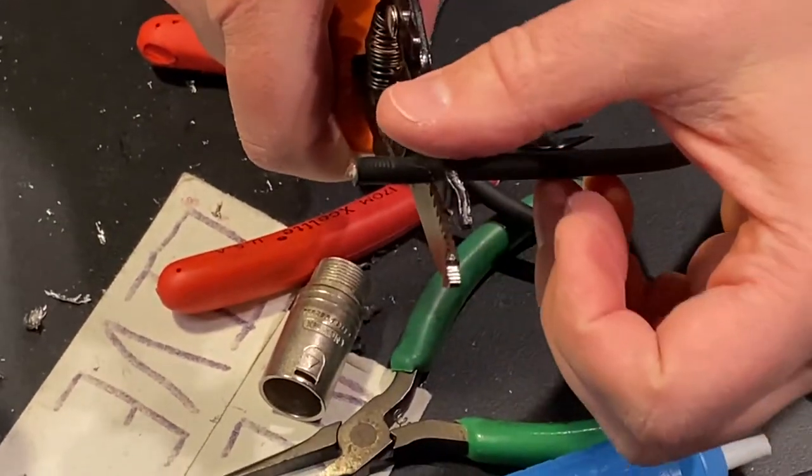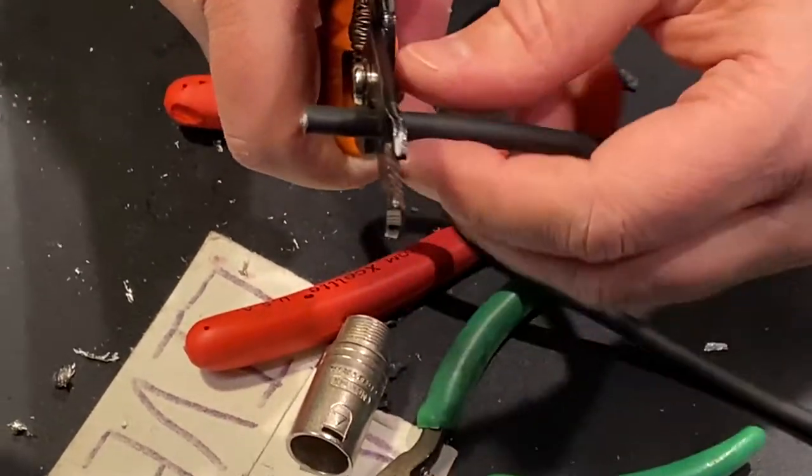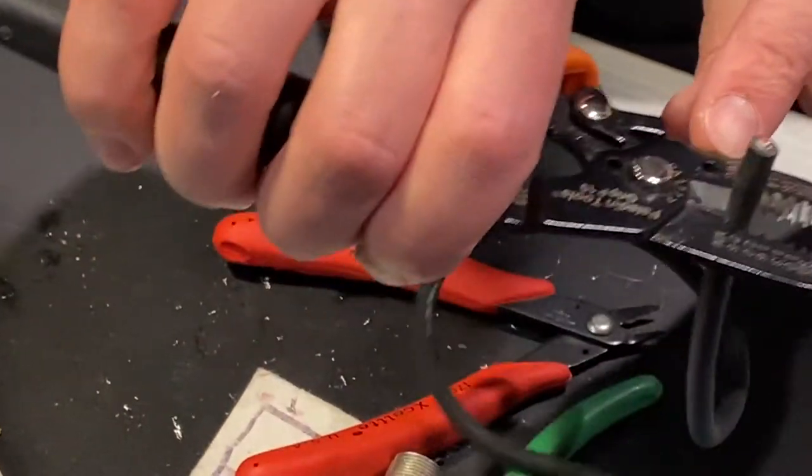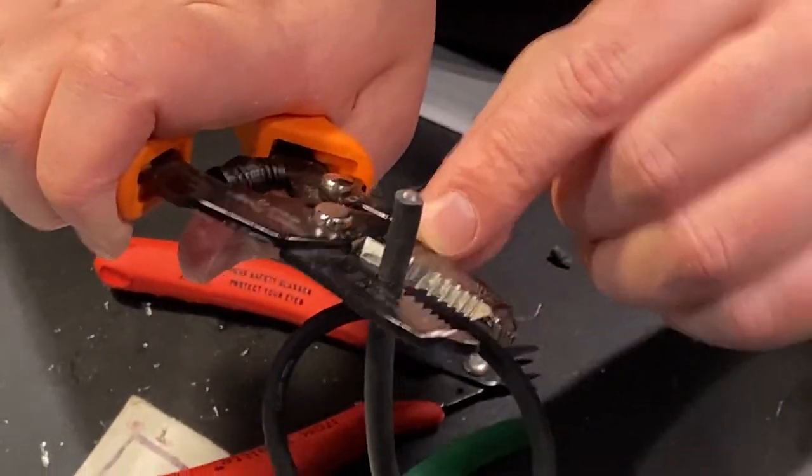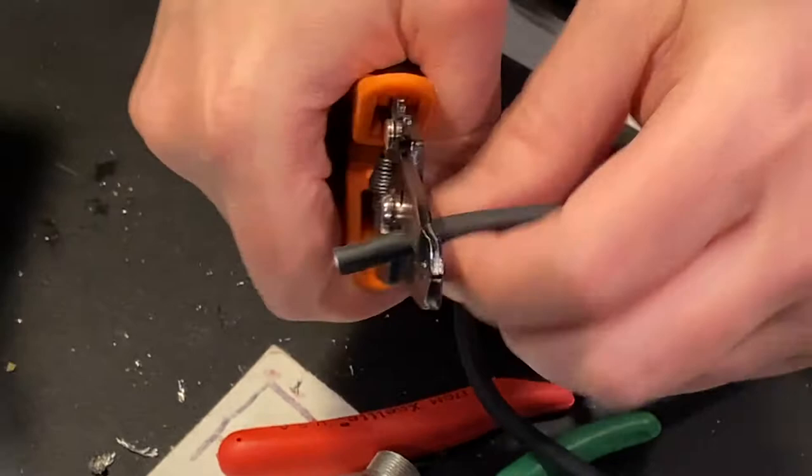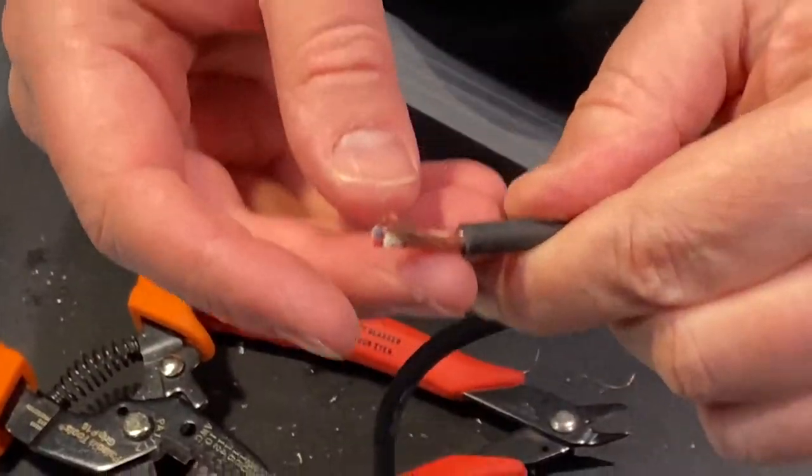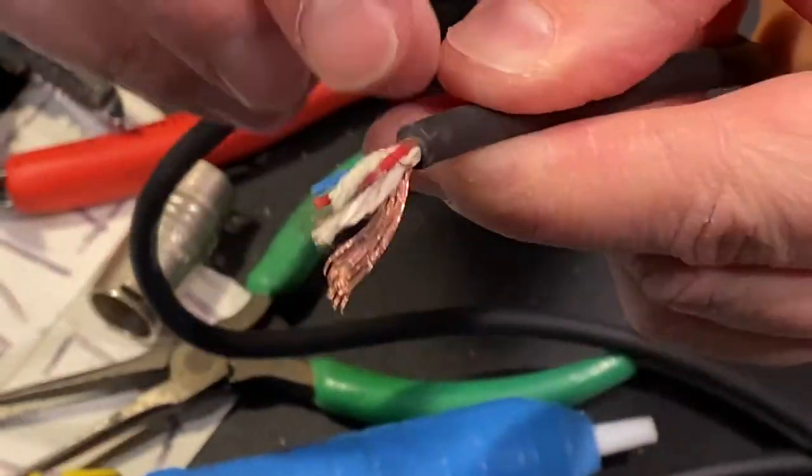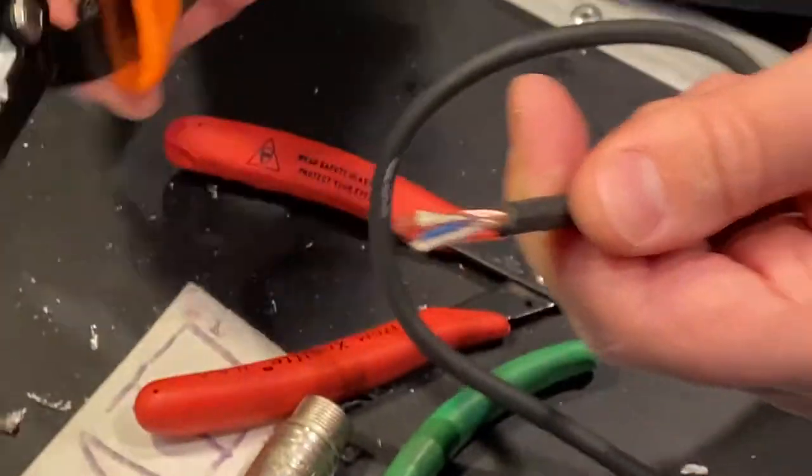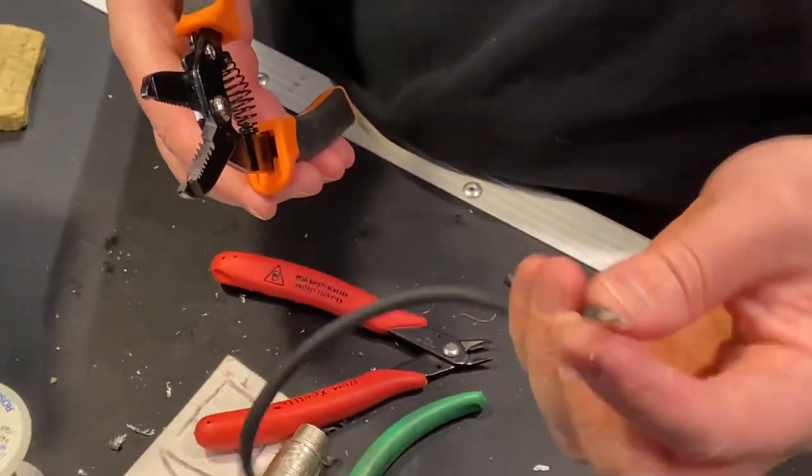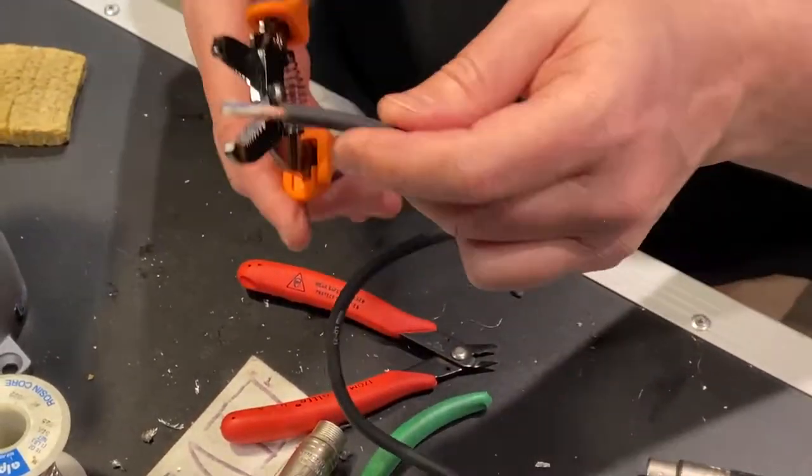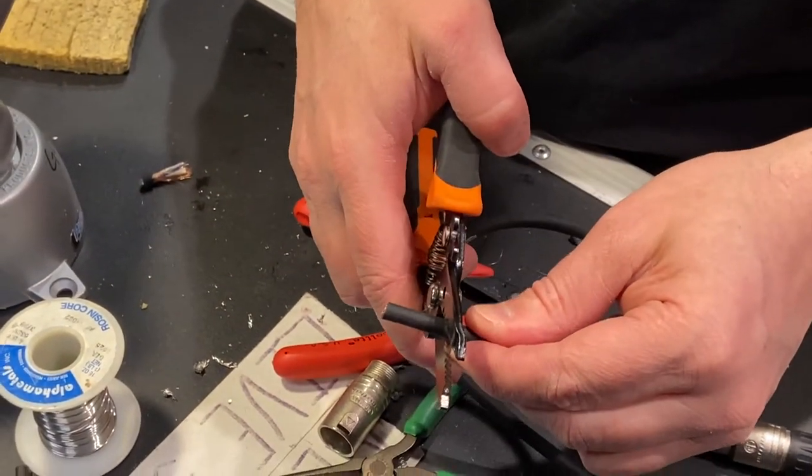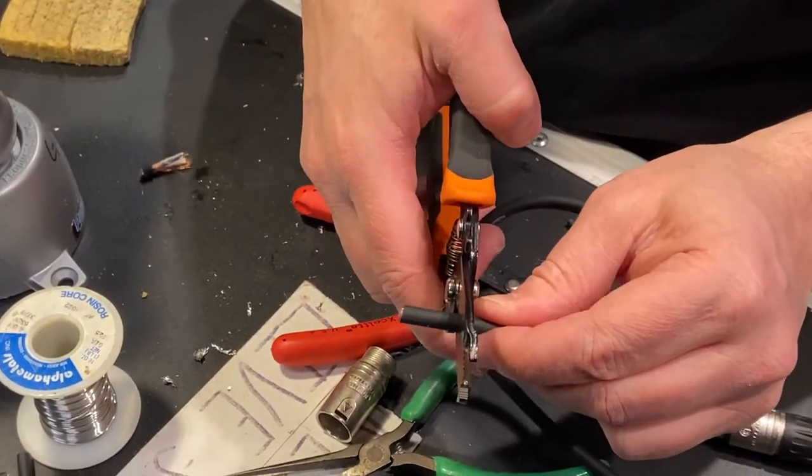I'm going to do this demo with the largest hole here, which is a 10 gauge wire. I can clamp and pull, but I felt it actually ripped some of the copper. It's cut there but not there. We don't want that. We want every last copper wire strand in here, especially with this cheaper wire which doesn't have a lot in there. I'm going to start fresh.